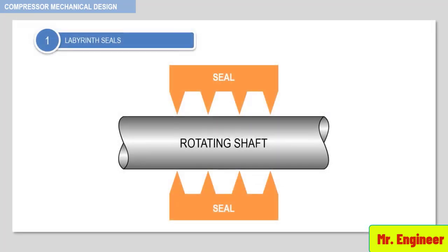The most common type of compressor seal is the labyrinth seal. It is most prevalent on air compressors and some gas applications. The sealing action is achieved by means of labyrinth teeth, which restrict the flow of gas. The teeth do not touch the shaft but maintain a close clearance. They are made of soft metal so that the shaft is not damaged on accidental contact.